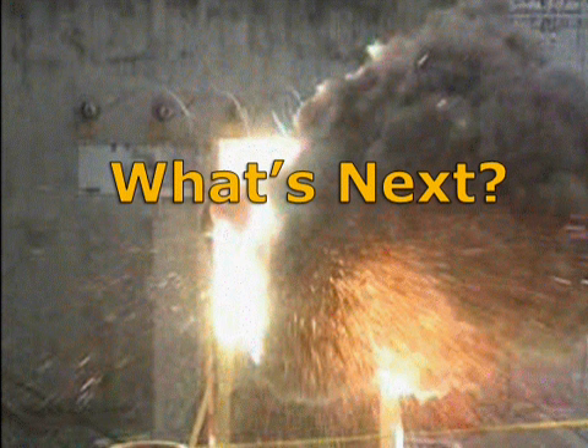If you look at arc flash and recent advancements, the one that comes to mind for me would be the ability to temporarily lower the parameter settings for either a breaker or a protective relay, so that when personnel are working on equipment, you can have those alternate parameter settings such that the breaker or the relay is going to detect a fault and clear that fault quicker. You basically want to have your pickup setting. Typically, it's going to be reducing the instantaneous. That typically gets you the biggest bang for the buck.